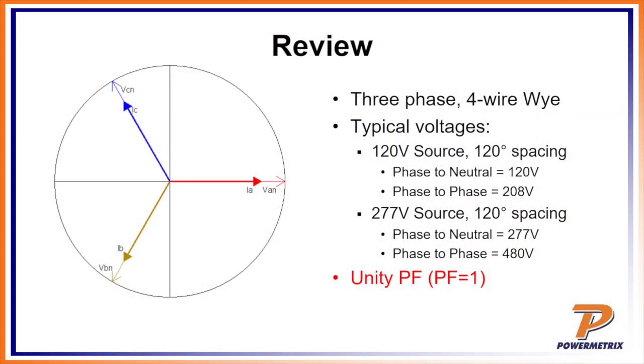So a 16S meter is a 3-phase, 4-wire Y. You've got basically two typical voltages: a 120 volt source with 3 legs at 120 degree spacing. With a voltmeter, if you measured A to neutral, you'd get 120 volts per leg, and if you measured phase to phase, like A to B or A to C, you'd get 208 volts, measured coming into the meter from the distribution side. Now if you had a 277/480 tap, similarly, phase to neutral would be 277 volts, and phase to phase would be 480 volts. In this vector diagram, we're showing this at unity power factor.